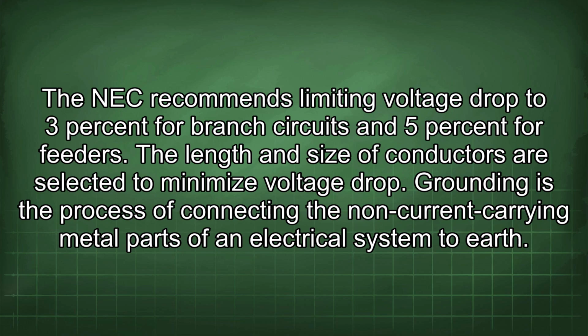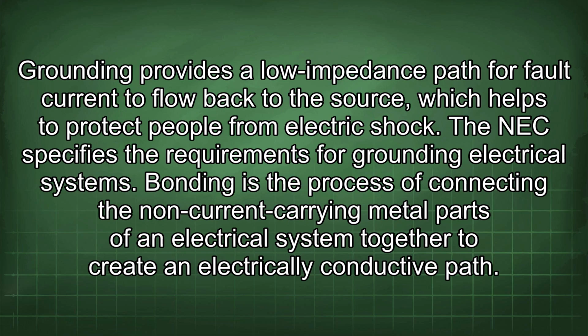Grounding is the process of connecting the non-current carrying metal parts of an electrical system to earth. Grounding provides a low impedance path for fault current to flow back to the source, which helps to protect people from electric shock. The NEC specifies the requirements for grounding electrical systems.